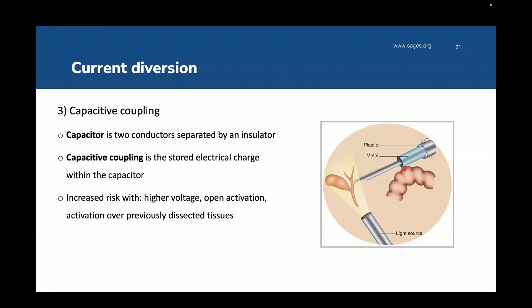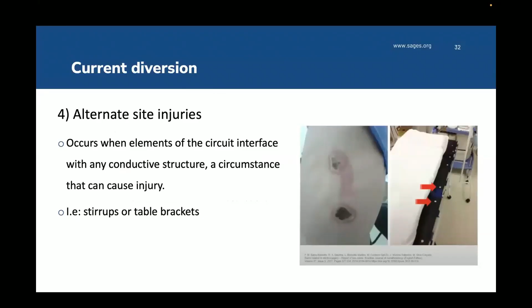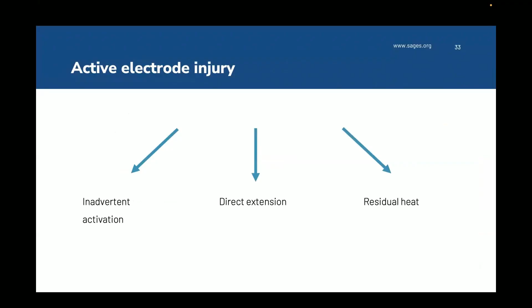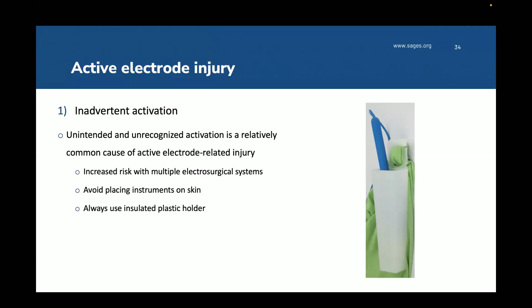Alternate site injuries. This is from a case report where a patient was burnt through conductive elements on the patient's bed. That can also happen with stirrups. Active electrode injury: again, three categories of this: inadvertent activation, direct extension, or residual heat. Inadvertent activation, in my mind, is like a never event. This just means that you've activated your instrument when it's out of view or when you didn't intend to. If the instrument is lying on the patient's skin or their face, it can lead to burns. So please always use a plastic insulator when you're not using the instrument.